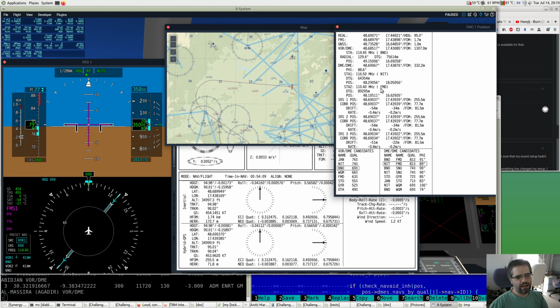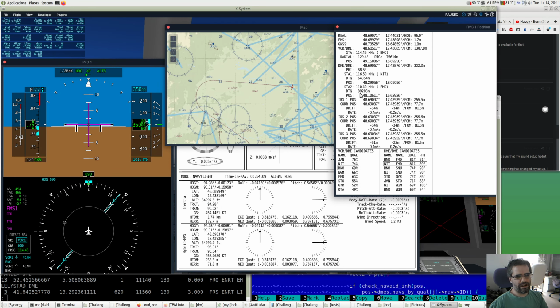But the problem is, just knowing the station value or frequency does not mean you're actually receiving the station. So what the system does is listen for about 5 seconds. It takes about 5 to 7 seconds for the audio ID to come through on the received signal, and it'll check that the audio ID matches what we expect to see in the database. If I look for FMD, we'd expect this audio ID on frequency 110.40. So it'll tune that in, see the radio reading it, get a distance-to-go value, but wait until that audio ID is confirmed. Only then will it trust that distance-to-go value.